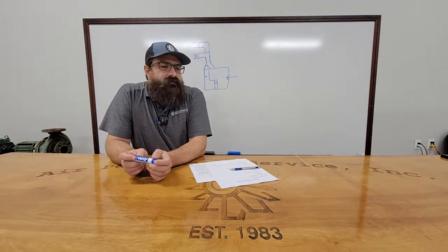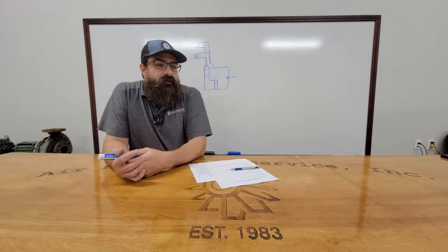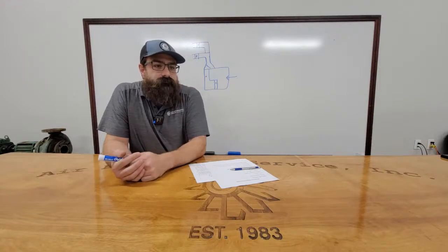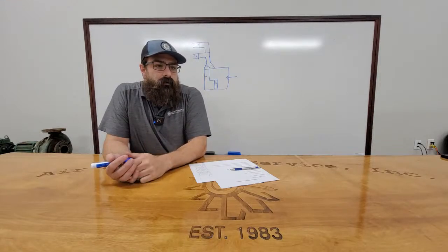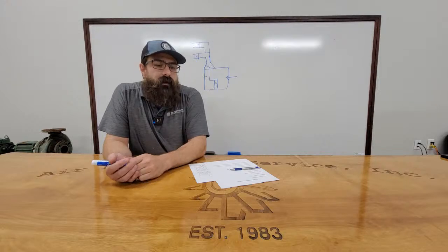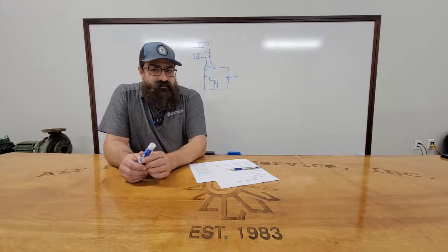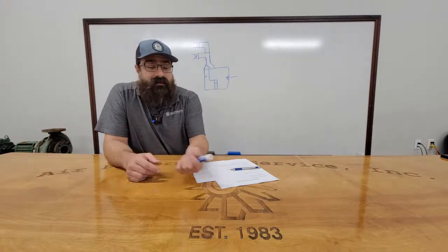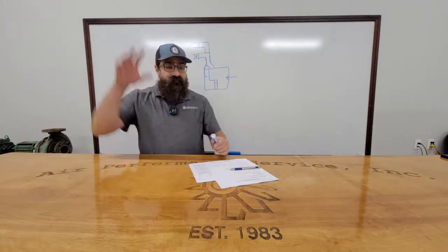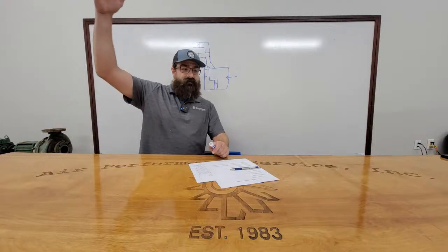So they just brought it into the return plenum. You just have open ducts in various little spots, and it's 10 degrees outside, so you're kicking on the burners, but you're only maintaining a 70-degree discharge air. Yeah, I mean, it's there. I don't know of many systems that just dump it into the return, but like I said, with this unit I was working on, it has a VAV box, right? And it's doing that as well.